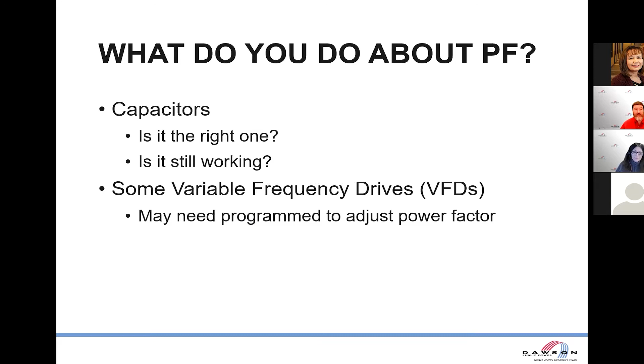Now, you don't have to correct your power factor. If you're okay paying a little extra because your power factor is below 90%, that's fine. Dawson Power will take that additional charge and we will use it to buy power factor correction equipment on our side of the meter. So here's a couple examples, right? The guy on the left here has a 98 horsepower motor with right about 60% power factor. So he's clocking in at 148 horsepower roughly.